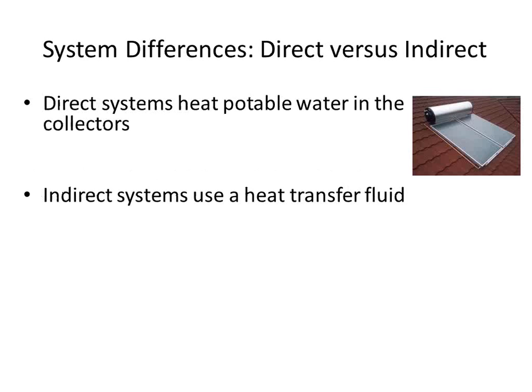Okay, the biggest difference is direct versus indirect systems. Direct systems will heat potable water in the collectors themselves. So basically, you're going to take the water you're going to drink. It's going to get plumbed up to the roof, where it will be in the collectors. The sun hits it, gets it hot. It comes back down into your system, and you use it in the home. Indirect systems don't do that. Indirect systems keep the potable water inside the home and use a heat transfer fluid, usually glycol, to go up to the roof, get hot, and come down into the basement, where it will then heat the water.